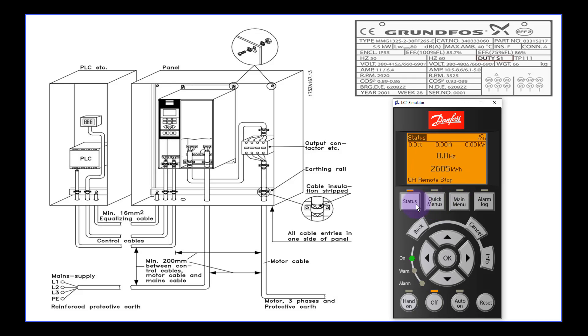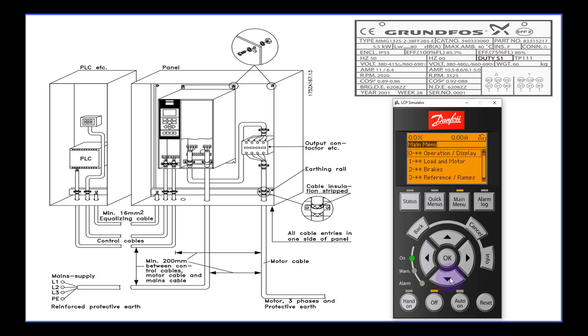Let's say you have completed the initialization. Then we go to key in all the motor data based on the motor nameplate. Press the main menu button — before doing that, make sure the off button is selected to ensure the VFD is not running. Press the main menu button. If you do not see the main menu home page, press it one more time. Then press the down arrow key to select 'load and motor,' then press the OK button.